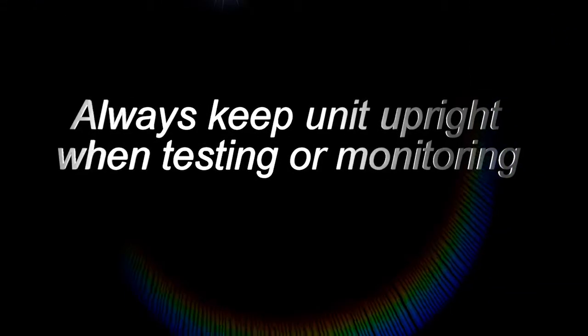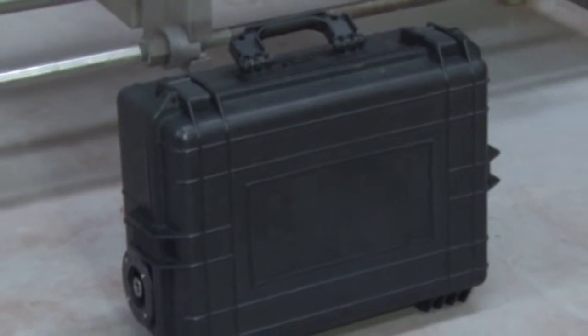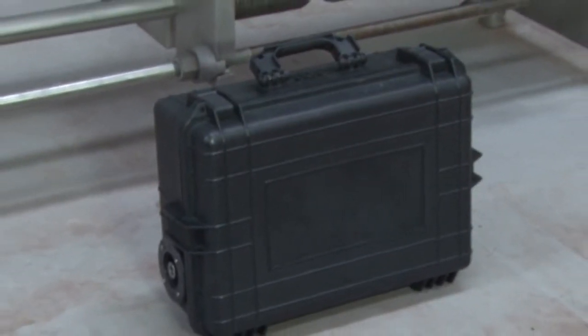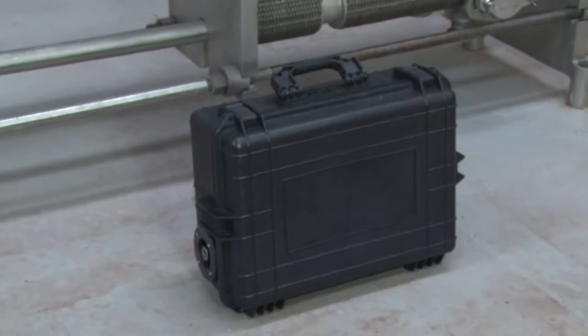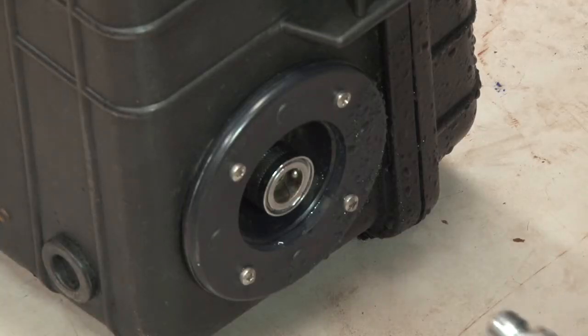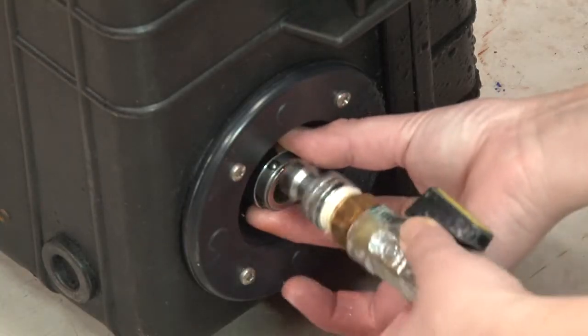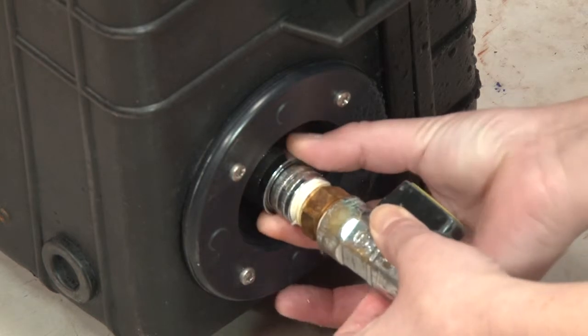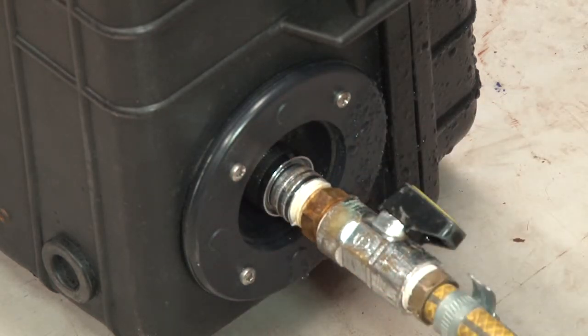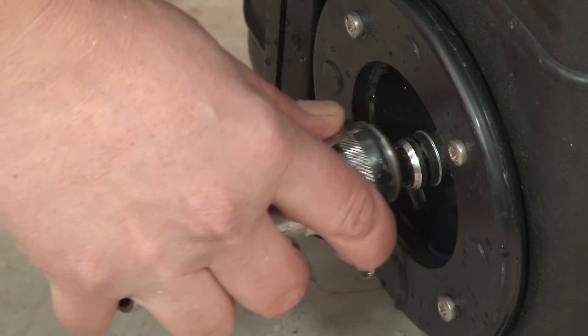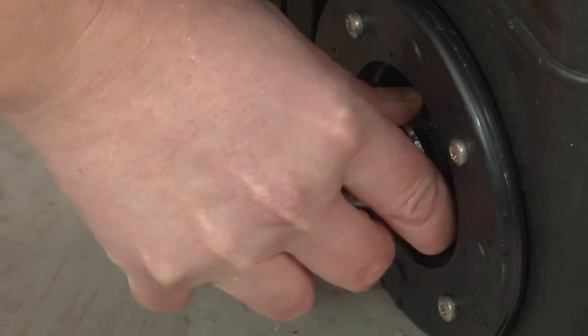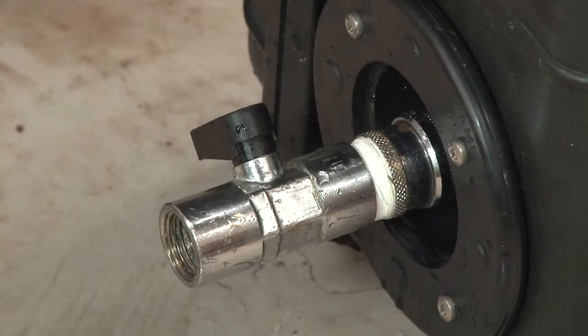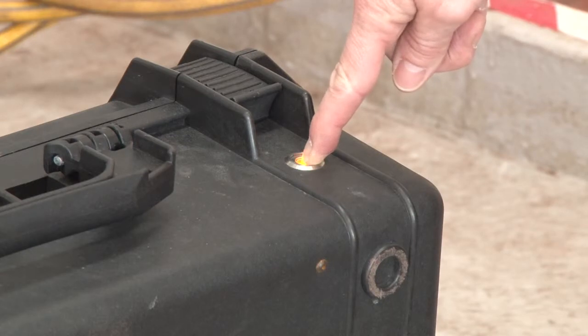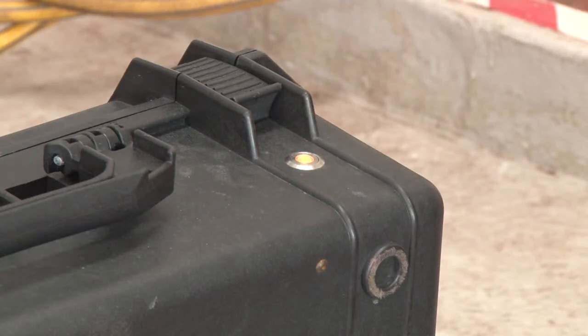When carrying out the test procedure, it is important to have the black box in an upright position where it cannot rock or be subject to vibration, as shown here. Connect main water via the inlet valve. Connect the stop valve. To turn on the unit, press and hold the switch for 2 seconds.